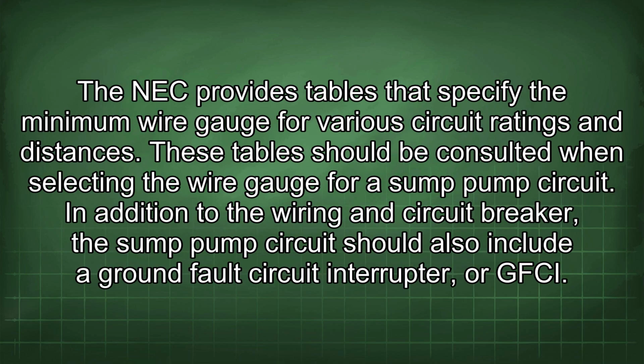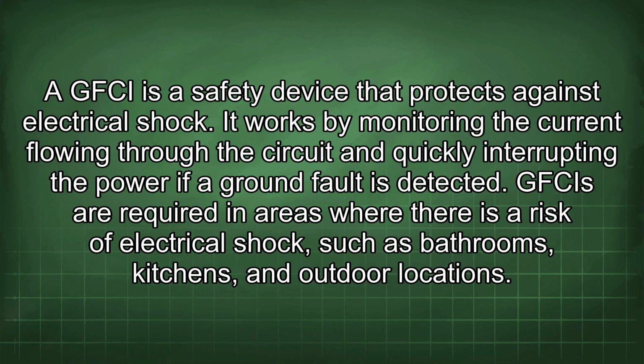The NEC provides tables that specify the minimum wire gauge for various circuit ratings and distances. These tables should be consulted when selecting the wire gauge for a sump pump circuit. In addition to the wiring and circuit breaker, the sump pump circuit should also include a ground fault circuit interrupter, or GFCI. A GFCI is a safety device that protects against electrical shock.